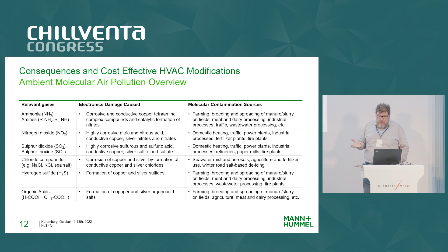Organic acids, again, your manure, okay? So the question is, do I just have to watch this and basically my data center goes down, and is there nothing I can do? Actually not. It's easy. Number one is you need to test the air quality. And that means every time, all the time, for the lifetime of your data center, everywhere you have critical operations, you need to monitor the rooms where there's critical equipment, electrical equipment, power supplies. And then you say, okay, I have to replace or add to the particle filters that I need for my clean room performance. I just need to add some simple chemical filters.